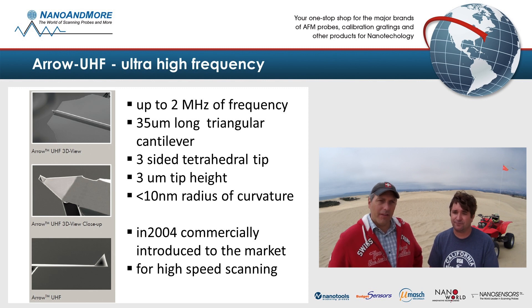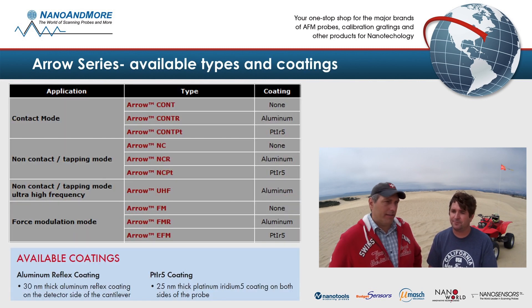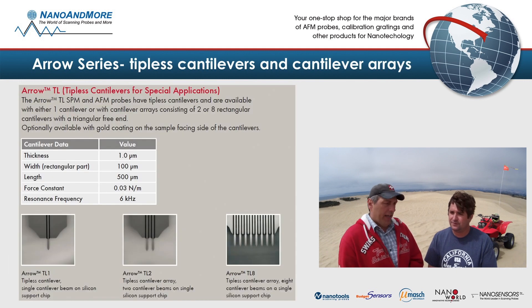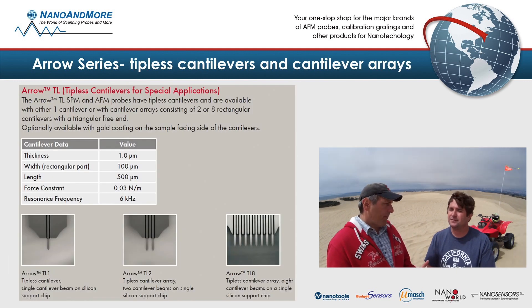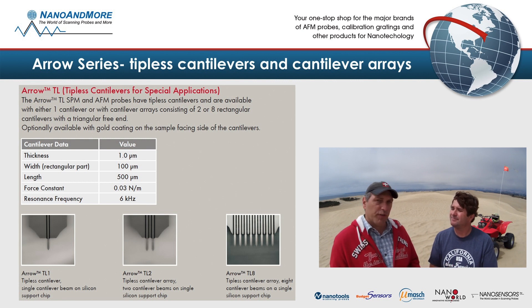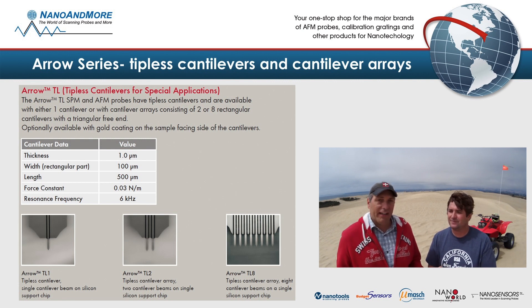The Arrow series solves a lot of problems and we have it for almost all applications: tapping mode, non-contact, force modulation, and contact mode. We have platinum iridium coating for all the conductive modes, and aluminum coating for enhancing the reflectivity of the laser. We also have tipless versions, tuning fork double cantilevers, or arrays of eight cantilevers for sniffer applications. So all is there.